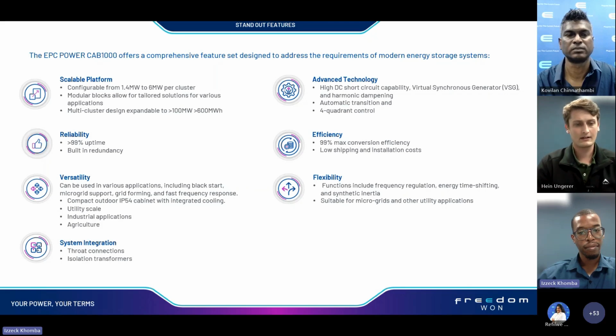The system can be integrated with a throat connected option, where the bus bars run through the middle of the inverter and then connect to your isolation transformer. Or there's the non-throated option where the cables terminate on the bottom through a trench. Some of the advanced technology built in is a high short circuit capability on the DC and the AC side. It can act as a virtual synchronous generator with synthetic inertia, and it can also assist with power quality downstream.